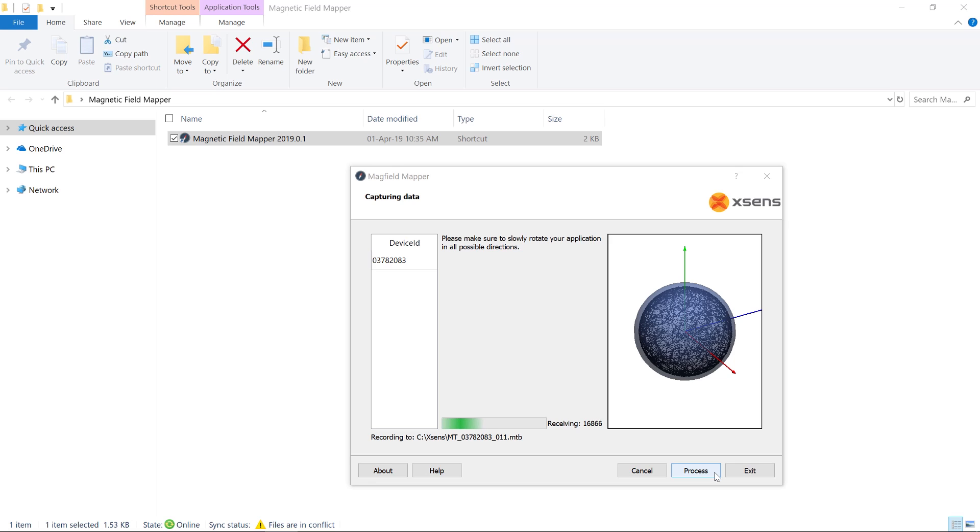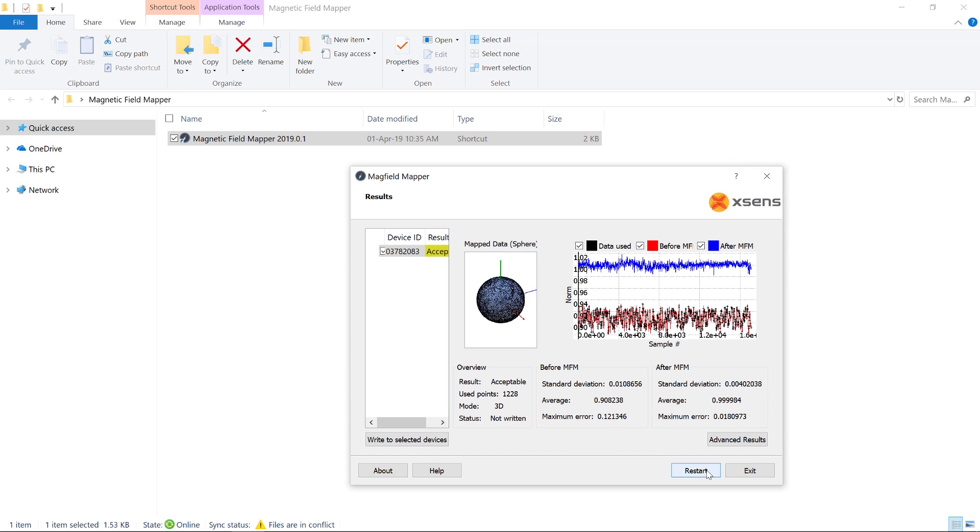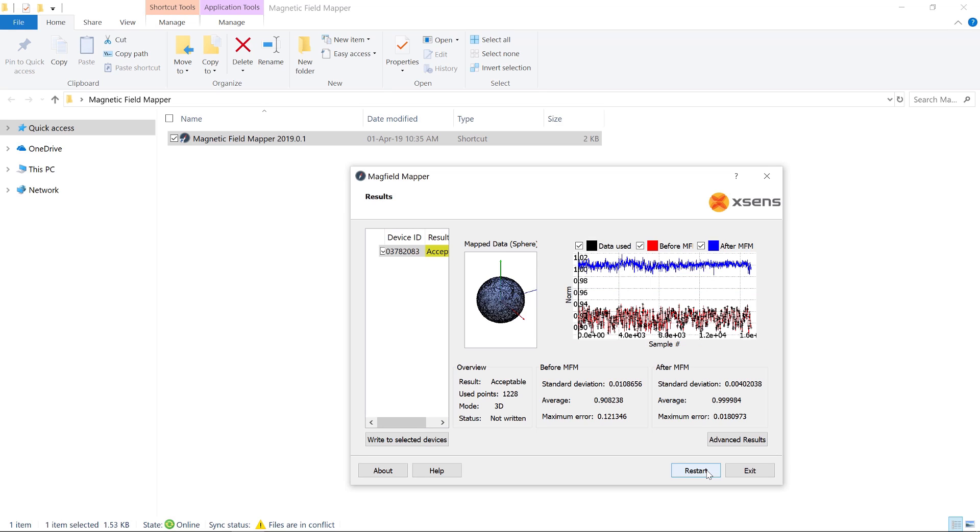Once you have collected a sufficient amount of data, click Process. The magnetic field mapper will run its calibration algorithm on the data set, and a results page will show up. The first result to note is the plot on the right, showing the magnetic norm before the calibration, in red, and after the calibration, in blue. We can clearly see that in contrast to the red line, the blue line is stable and close to 1.